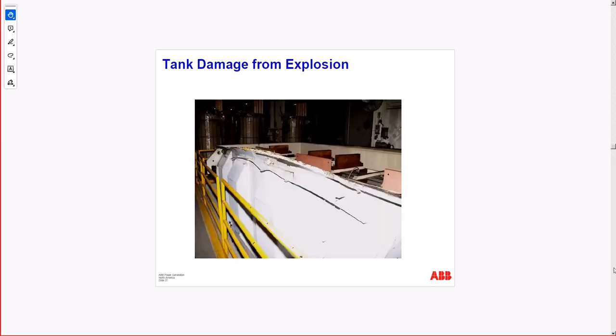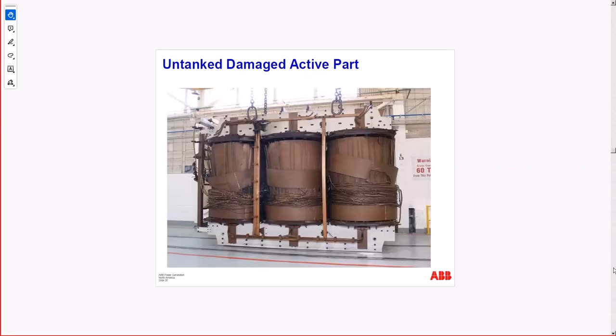Tank damage from explosion. Well, an explosion comes with chemical products that need to be cleaned up, which is very costly. Plus, the explosion is permanent damage to the equipment, and it is dangerous to the workers and the public. So it can catch fire, and then you get high temperatures developed, a few hundred, 400, 500, even 700 Celsius.